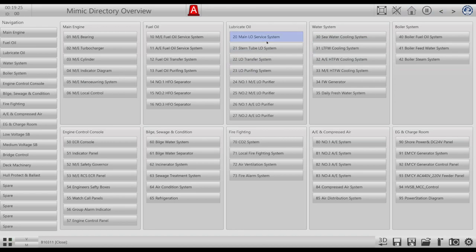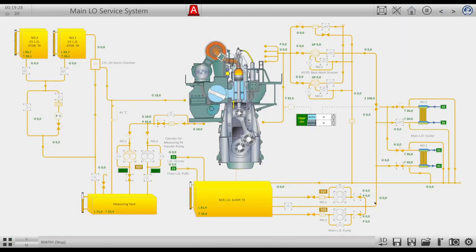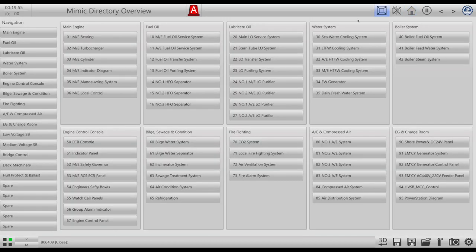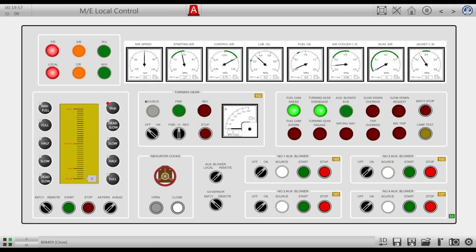Okay, let's go back to where we left off with the lubrication part. So these freshwater coolers are now set. The temperature is controlled via this control valve, this bypass valve. It's in auto mode, so that's okay. Let's open this valve, and now we have a complete circuit and we can start this main lubrication pump. We do have pressure and flow, so that's okay. Let's put the second pump in remote.